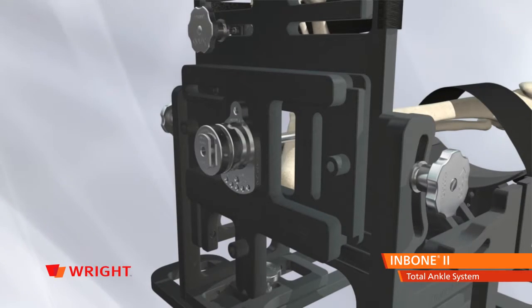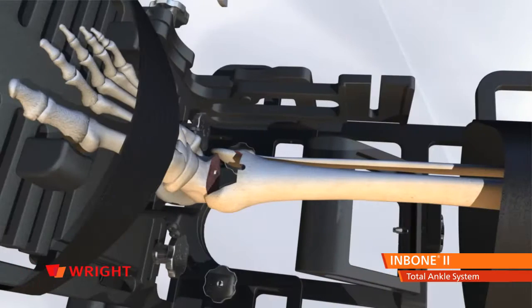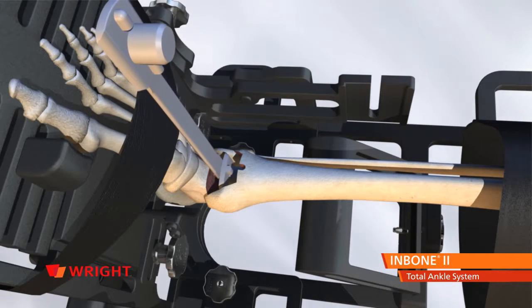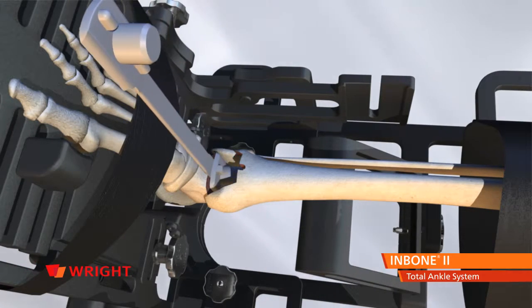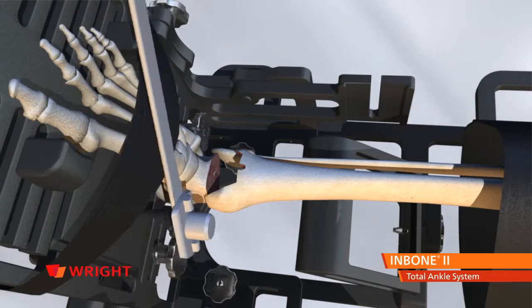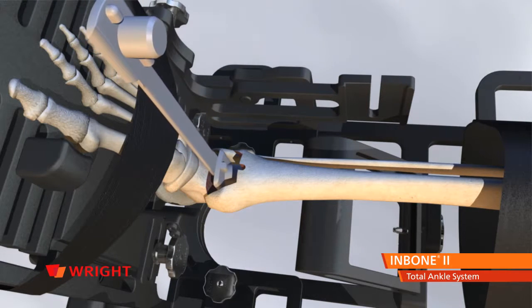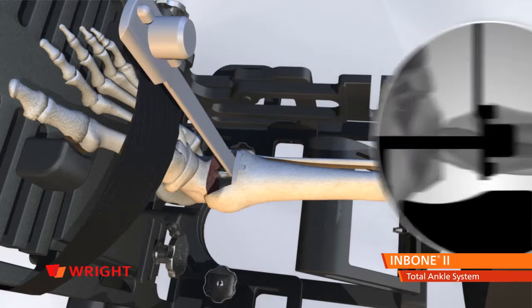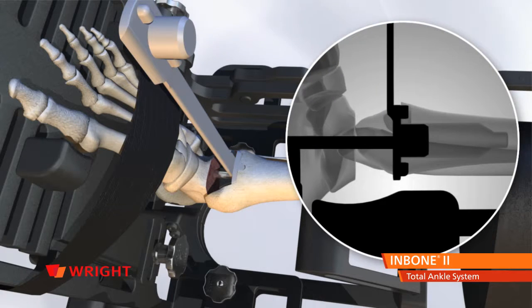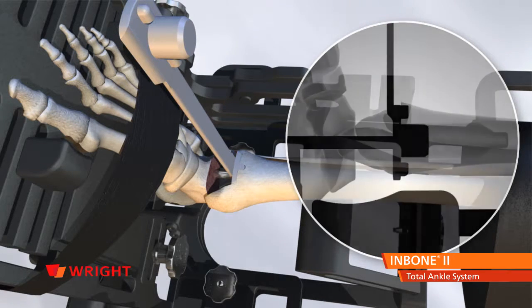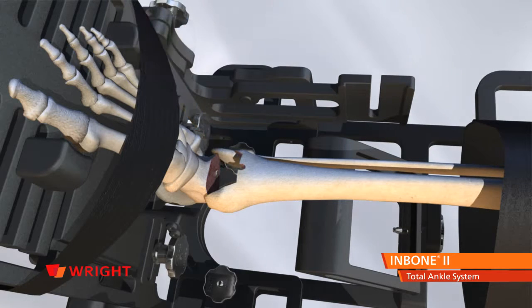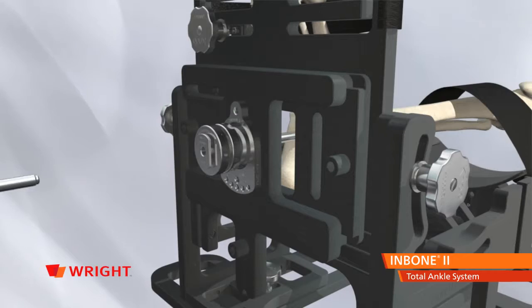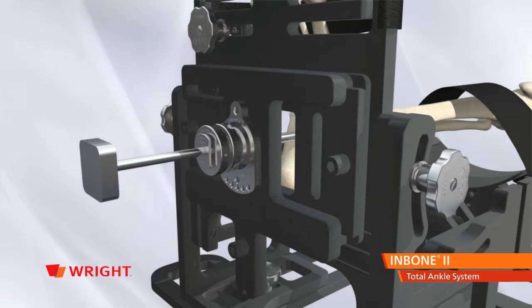Remove the drive rod and replace it with the strike rod. Select the appropriate sized tibial tray AP sizer and insert into the resected joint space. Use both ends of the sizing tool to determine the optimum AP size for the tibial tray, standard or long. The strike rod can be used to fully seat the tibial tray sizer into the tibial resection. Remove the strike rod and replace it with the X drive.